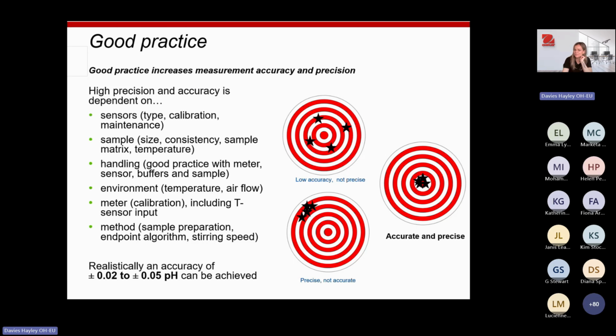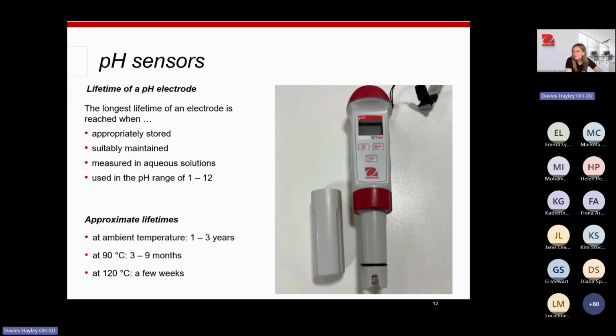So this next slide might shock you then. The lifetime of a pH electrode. So the longest lifetime of an electrode is reached when you've done everything correctly to the letter, when you've stored it properly, when you've maintained it properly as well. So you've been calibrating it, it's been stored correctly. If you're measuring in aqueous solutions, which I'm assuming 99% of the samples that you're measuring are going to be, because if it's not aqueous solutions, you probably need a specialist electrode or a different type of electrode. And if you use it within the range of pH 1 to 12.